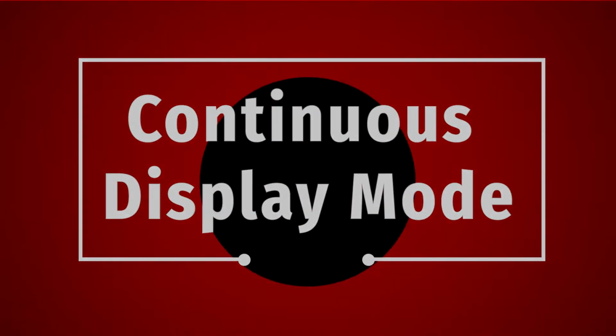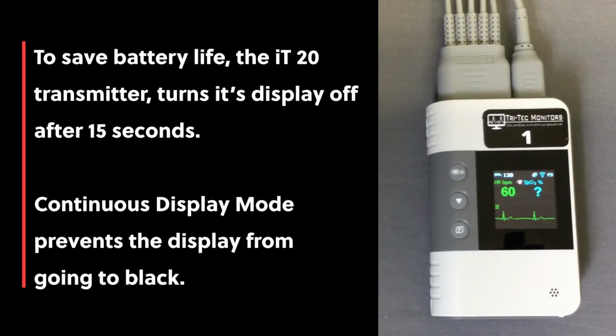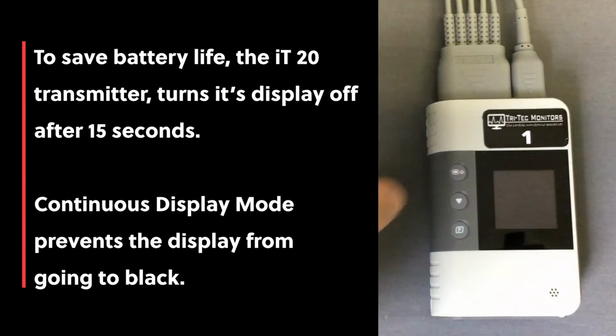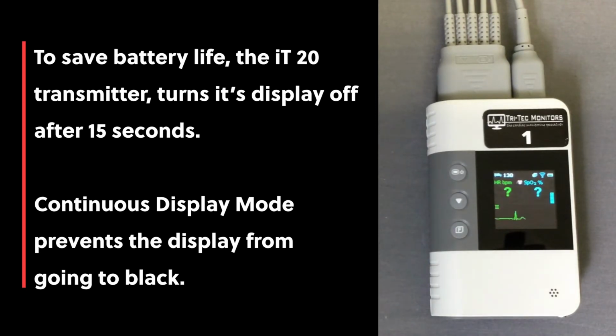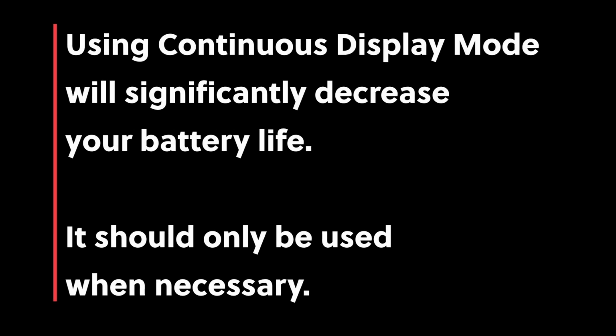Continuous display mode. A great feature of the IT20 telemetry transmitter is continuous display mode. To save battery life, the IT20 transmitter turns its display off after 15 seconds. But there may be times when you wish to monitor patient waveforms directly from the transmitter. Continuous display mode will keep the screen from turning off and going black. Important: using continuous display mode will significantly decrease your battery life, and should be used only when necessary.